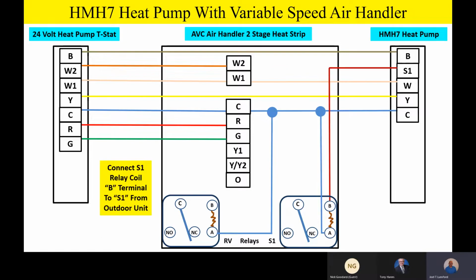On the S1 relay, we're going to take the other side of the relay coil and take it to the S1 on the outdoor unit. So that's going to be our airflow reduction relay. The common of the switching contacts on the S1 relay is going to go up to yellow, or the compressor call, like we did before. Normally closed is going to go to Y/Y2. That's our high-speed airflow.